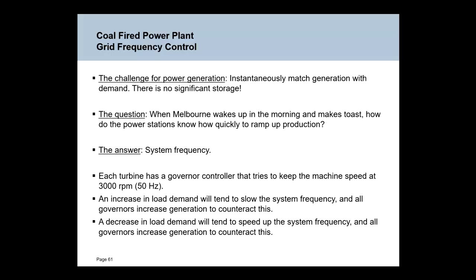There's no storage, okay? So if you and I get up in the morning and turn our toasters on and we're consuming more power, how does the power station in the Latrobe Valley know they've got to produce that increment more energy to keep the grid in balance? Okay. The answer is system frequency. Okay. So this whole system, as we said, is spinning at 3,000 RPM, which equals 50 hertz on our AC power that comes out of the power socket. As we turn on lights and toasters and everything else, that additional electrical load looks like a brake on the system. We're trying to slow the machine down. So you've got these 30 or 40 power station units around the country all generating into the grid, and by turning our toaster on, we're trying to slow the system down.